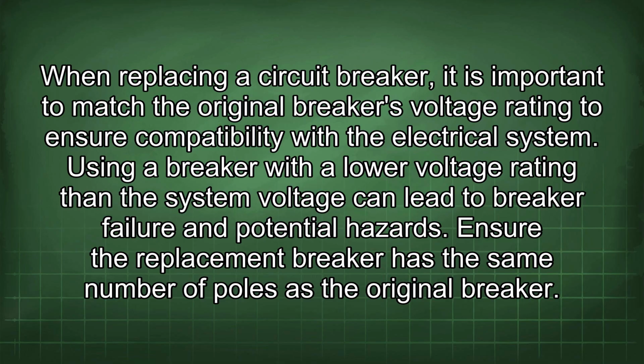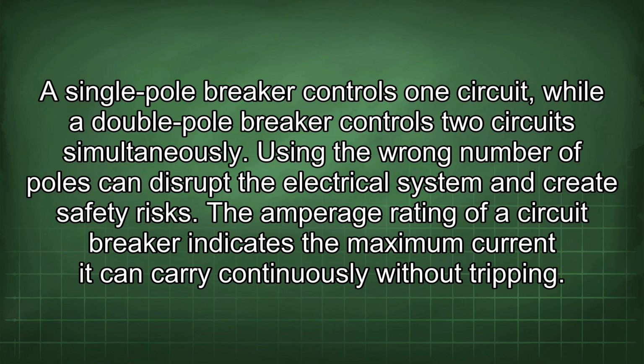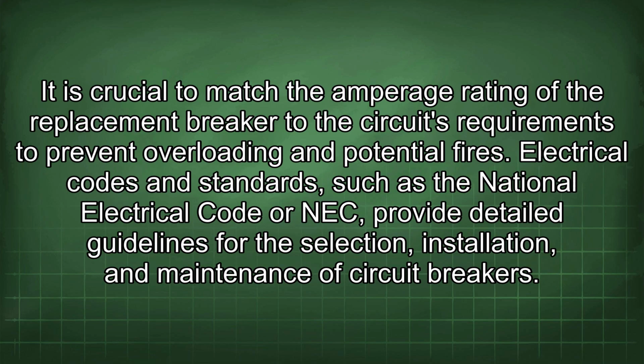When replacing a circuit breaker, it is important to match the original breaker's voltage rating to ensure compatibility with the electrical system. Using a breaker with a lower voltage rating than the system voltage can lead to breaker failure and potential hazards. Ensure the replacement breaker has the same number of poles as the original breaker. A single pole breaker controls one circuit, while a double pole breaker controls two circuits simultaneously. Using the wrong number of poles can disrupt the electrical system and create safety risks. The amperage rating of a circuit breaker indicates the maximum current it can carry continuously without tripping. It is crucial to match the amperage rating of the replacement breaker to the circuit's requirements to prevent overloading and potential fires.